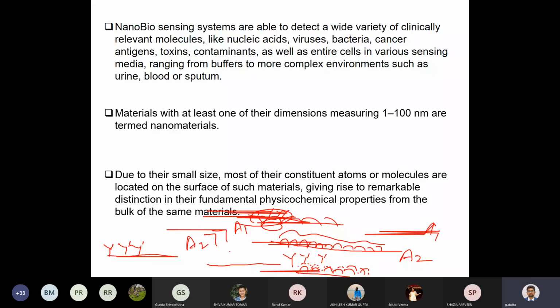This is one part, because you get the high surface area, and another part is conductivity. What is this? If you use some nanomaterial like gold nanomaterial or some metal-based nanomaterial, or even some carbon-based material, then the electrical conductivity transfer rate, I mean through the transducer, will be much higher. So you will get a higher signal compared to without nanomaterial. So this is another property. That's why we try to use some nanoparticles on the surface for development of the sensor.